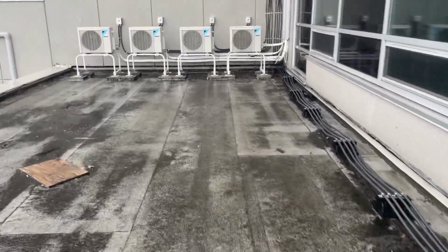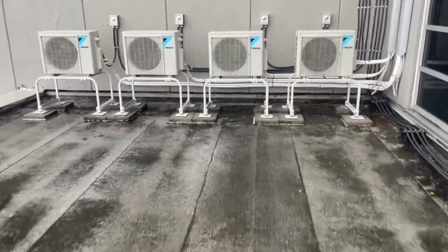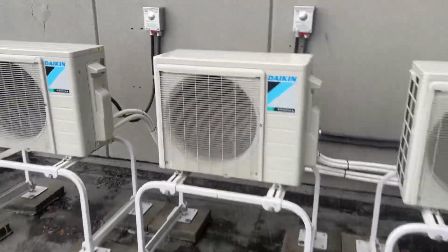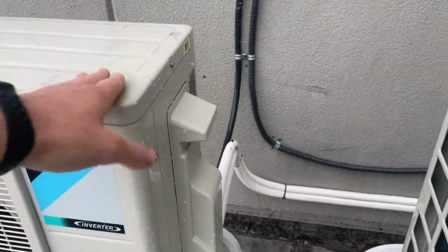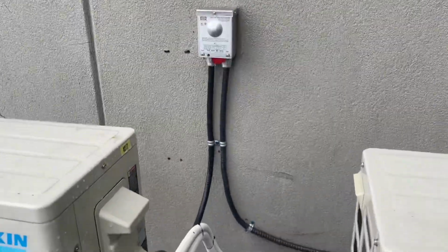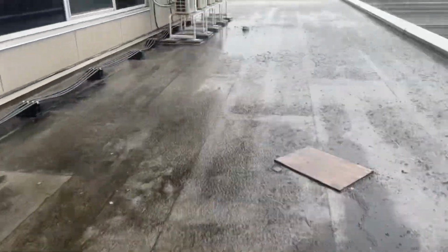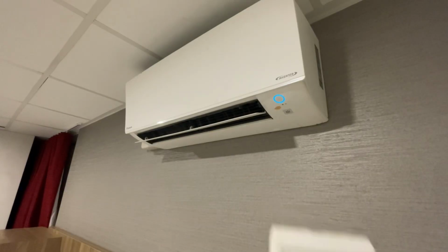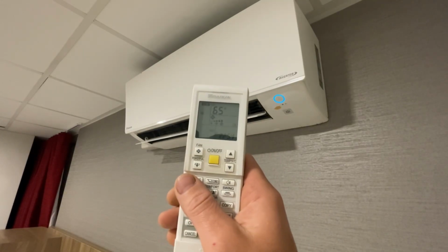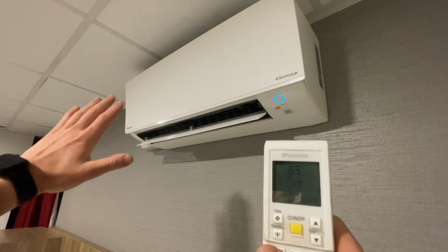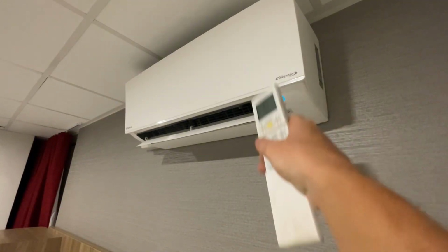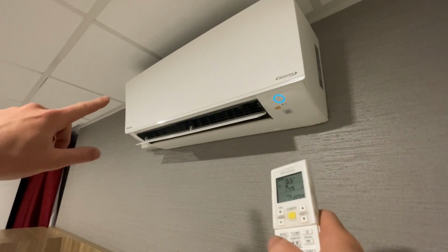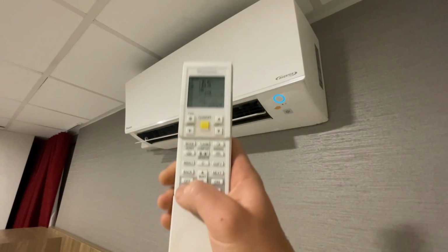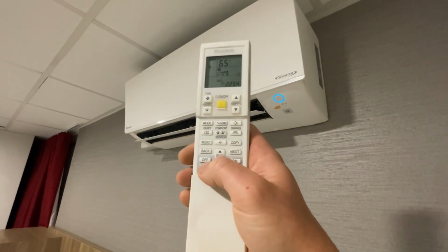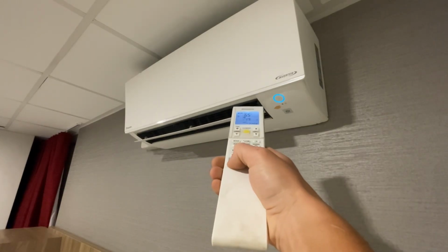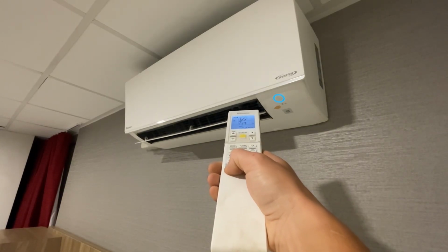Anyways, we're back here with our first call. We have another hotel suite unit that's giving us problems, so we're gonna go inside, take a look, see if we can wait out this rain. All right, as you can see, unit set to 65 degrees, cooling's on, fans running. Our indicator light is fine and solid, but our outdoor unit's not coming on, so let's see what kind of code we're generating here. We're gonna locate our cancel button, press it once, press and hold, aim at our system.